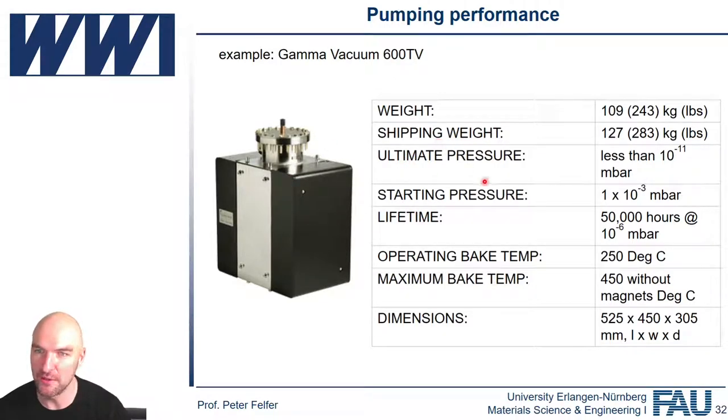But they're extremely robust in pumping. They're made for semiconductor equipment. So even if your vacuum would be 10 to the minus 6 millibars, they would live for 50,000 hours. So they live, and it linearly goes down with the pressure. So at the pressures we're working at, they're like new when you open them after 10, 15 years.